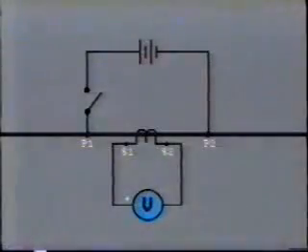The polarity markings should be checked on all CTs. One method is to apply the flick test in a similar manner to that discussed earlier for the voltage transformer. Preferably, the test lead should be passed through the CT donut as the primary conductor. If this is not possible, the small DC current will have to be passed through the primary conductor itself, like this.